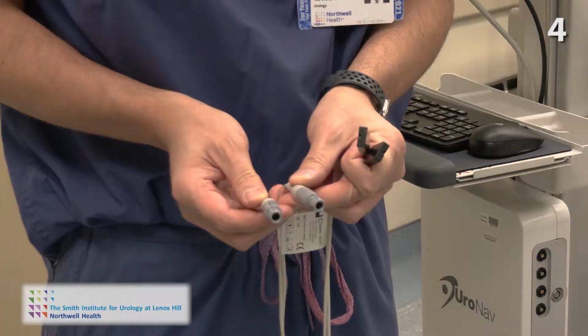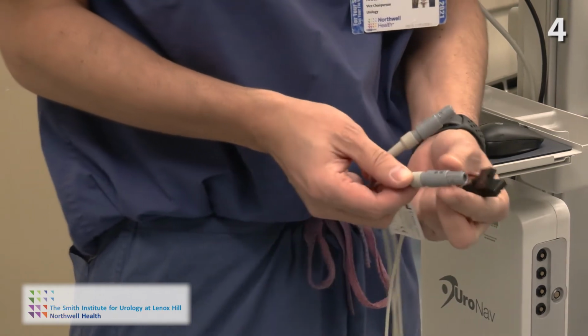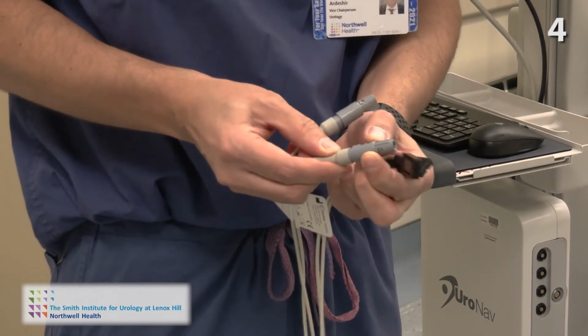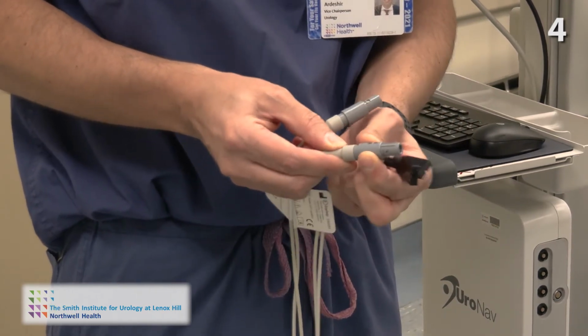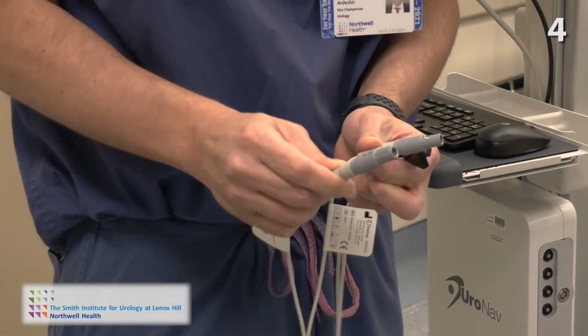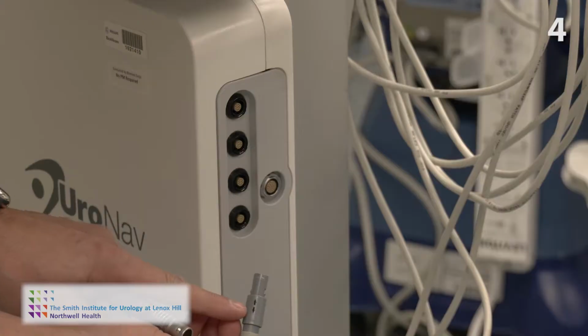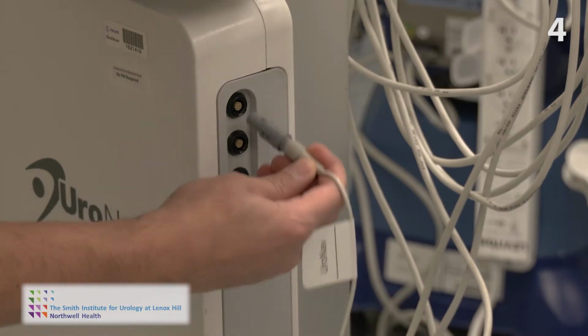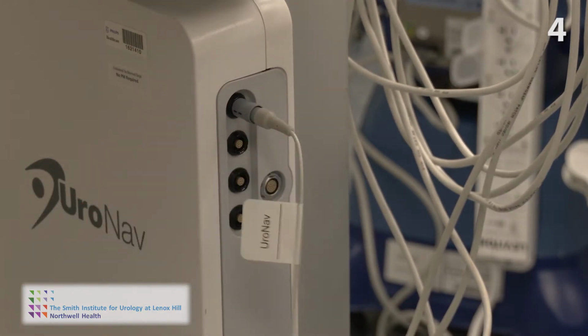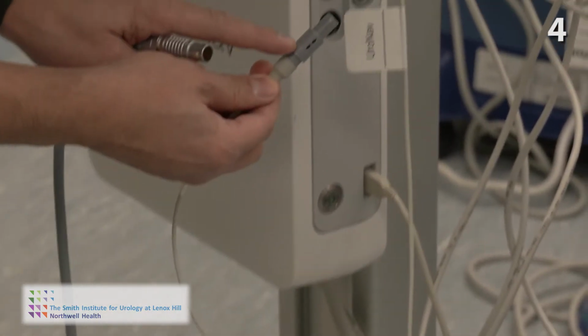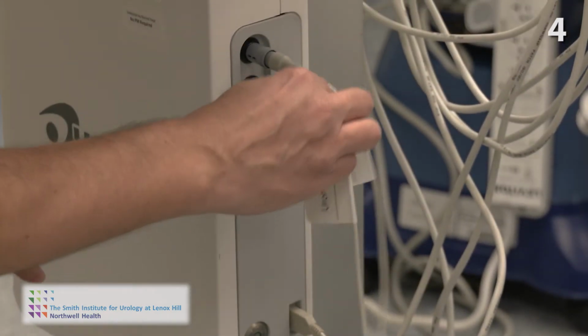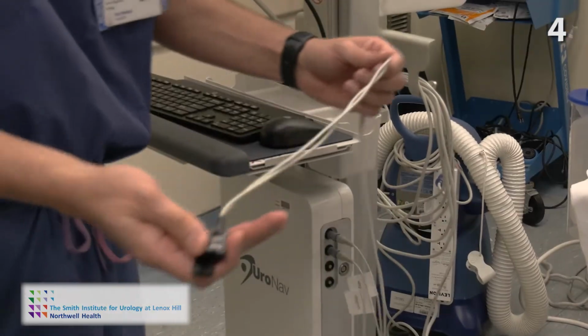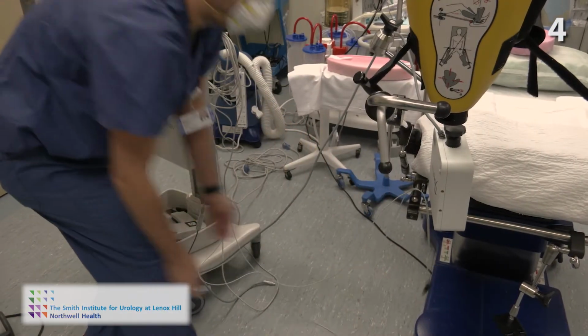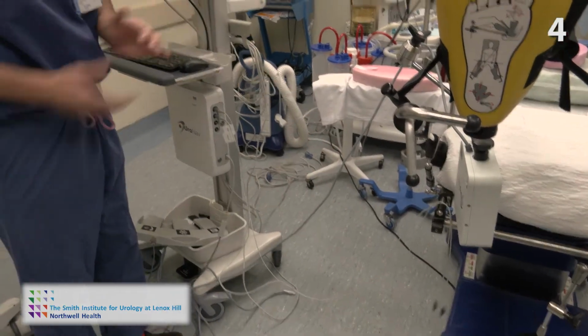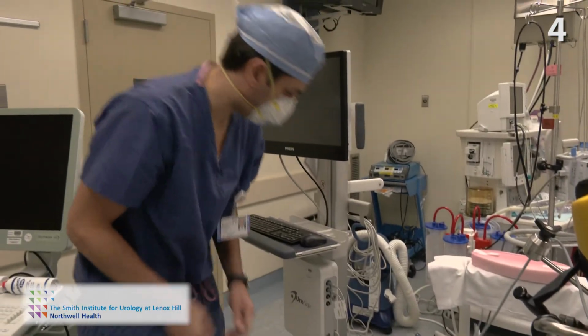These are the plugs that go into the UroNav device. I'll show you. The way they work is that they recess by pushing back to remove the lock. If you twist them in the device, you'll break them off. Looking at this, you see the black line lines up, faces you, plugs in. Again, the black line faces you, plugs in. And before the case is ready to go, we hang the trackers over the edge of the stabilizer bar here to allow them to be ready for the physician.